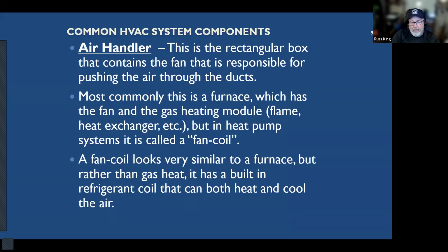Air handler. So the air handler is the big box that has the fan in it, and the purpose of that fan is to push air through the ducts. Whatever that box is, we call that the air handler. Okay. It can be a furnace. A furnace is an air handler. Okay. For heat pumps, we don't burn the gas. And so there's a fan and then the coils in the same box.